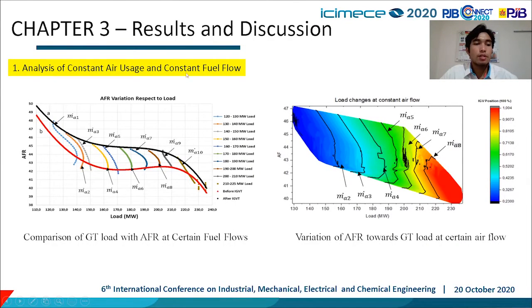Chapter 3, Results and Discussion. The analysis of constant air usage and constant fuel flow. The constant air usage and fuel flow variation formed a new curve of optimum values based on air to fuel ratio values after IGVT was performed. In this figure, it shows the variation of fuel flow and IGV opening generates the variation of gas turbine output power. The black line shows the higher limit position of air to fuel, and the red line shows the lower limit. It indicates a specific IGV position with stable airflow. If the fuel flow increases continuously, the output load power will also increase until reaching the maximum and then decrease.